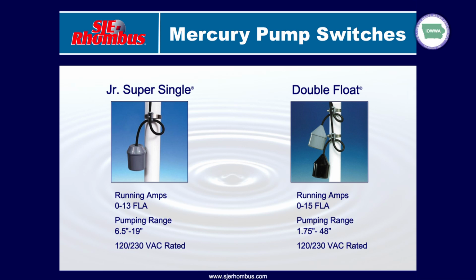Mercury switches are really what the industry was formed with, 30, 40, 50 years ago. A lot of states have gotten away from mercury. Mercury seems to be a dirty word, but I will say, as long as mercury is legal to put into a float switch, we'll offer them. The one thing we won't do is, if a state has outlawed mercury, we will not ship a mercury float into a non-mercury state. So keep that in mind. Iowa allows mercury switches, so that's still a viable option in this area.